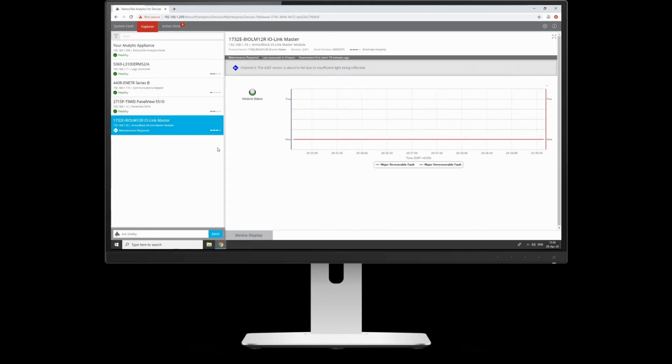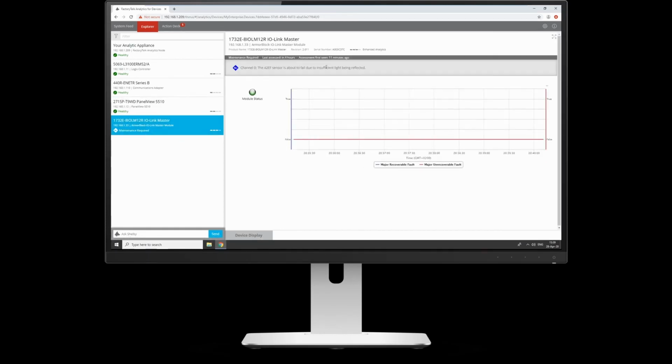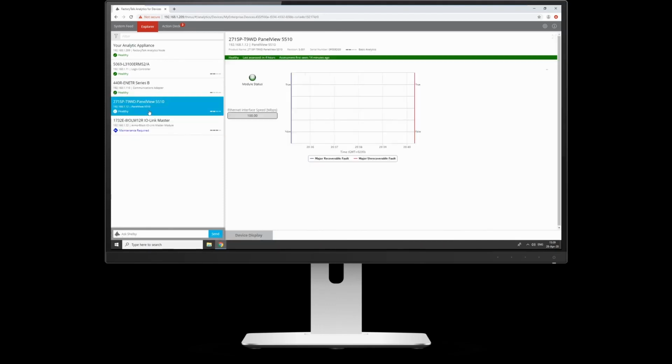Now, if we were to unplug that sensor, if you give me a second, I'll just go and unplug it. This is where you'll see that this is not real time, this box. It's not meant to replace alarming on your control system. It's sat there as a simple deploy supervisory system. It's additional to your alarming. So you wouldn't expect to be waiting for this to tell you that your sensor's failed. But in a minute or two, you should see that change to a higher level because the sensor's been disconnected. So it can be used to give you some warning, but don't use it as your primary measure for alarming.